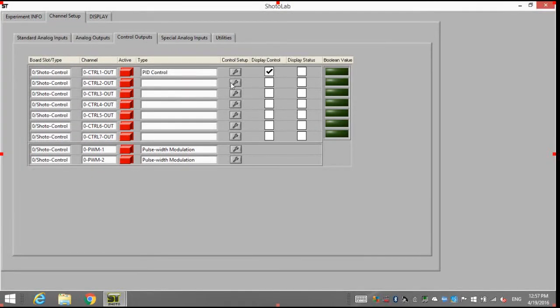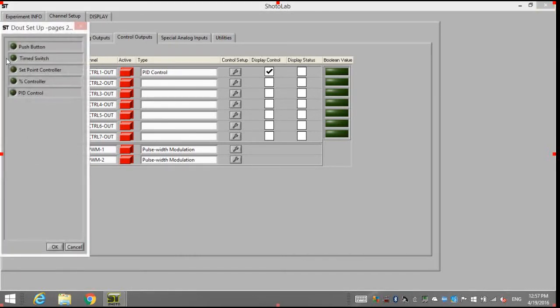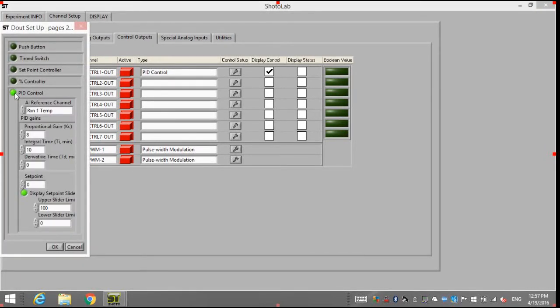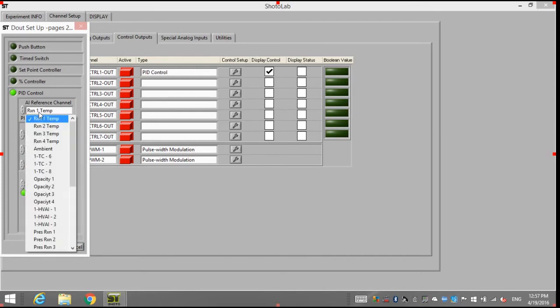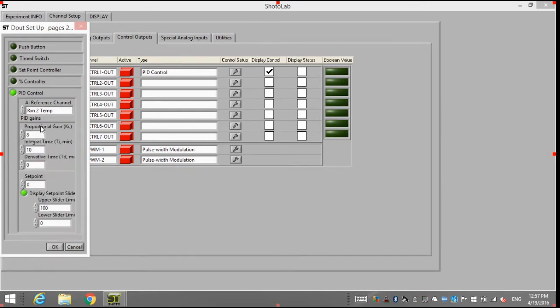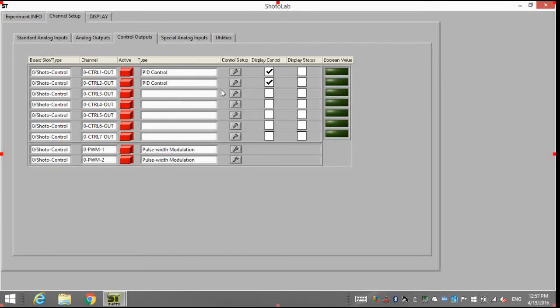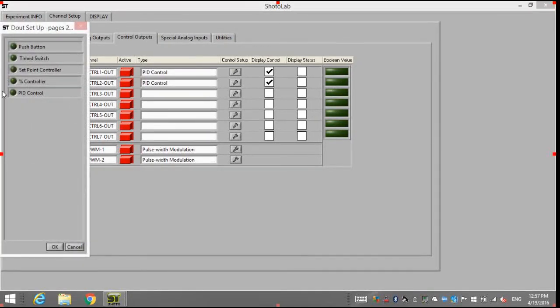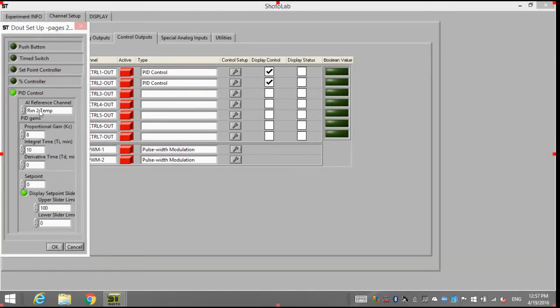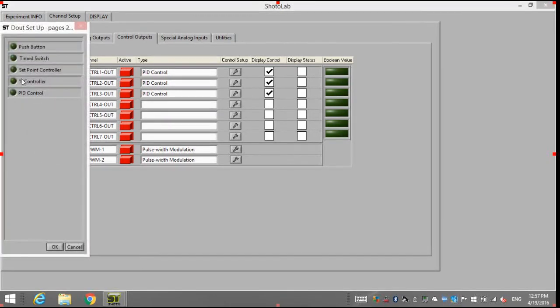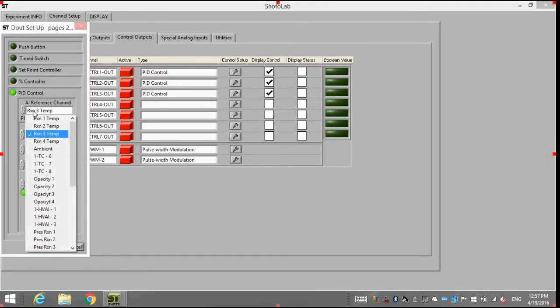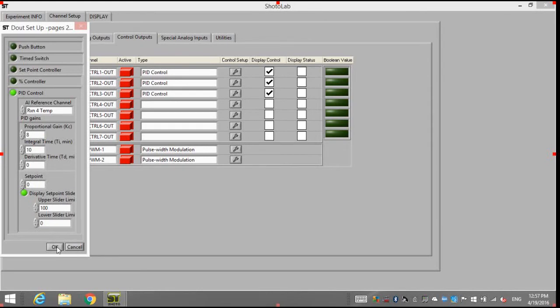Repeat this for the second channel, but this time you need to change the reference channel to the second reactor. This is the temperature the PID will be using for monitoring. You can keep everything else the same and press OK. Do the same for the third reactor. Again, change the analog input to the third reactor thermocouple. And again, everything else can be kept the same. And finally, the fourth channel. Click the wrench, choose PID, select the correct reference channel, and that is the fourth reaction temperature, and click OK.